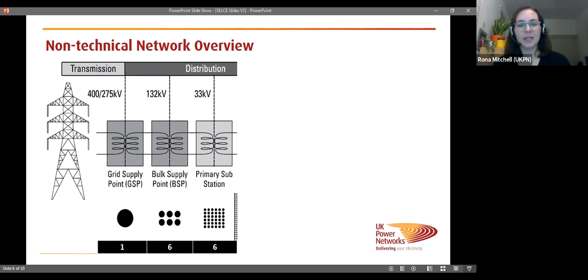We would then have the primary substations at 33,000 volts, with about 6 primary substations fed from a bulk supply point. That would then go to a secondary substation, the local ones, the little boxes you see around your walks. I've got a picture of one coming up in a minute - you'd have about 20 secondary substations fed from a primary, which would then feed between 100 and 200 homes.